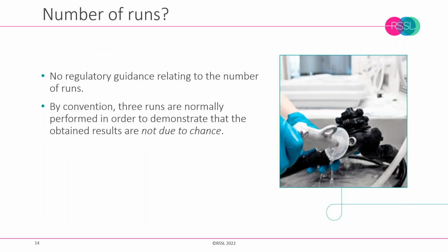Another factor that needs considering with any form of cleaning validation is how many times a cleaning validation exercise should be run. And as with any other form of validation, there's sometimes a recourse to the magic number of 3, which is normally the minimum acceptable level to demonstrate that the results obtained are not due to chance. But to stick only with 3 will assume that a process is consistent and that all the variables are in control. Where that can't be adequately demonstrated, so there may be variances of different types of product where worst case is not necessarily evident, then more than 3 runs would probably be required.